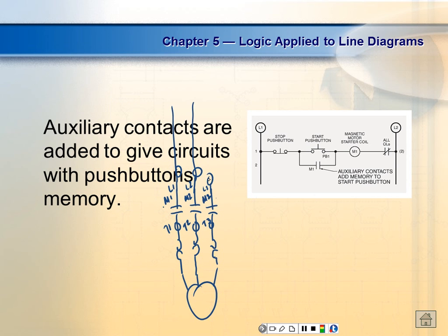what could the voltage be over here? 240, 480. Yeah, 480. So your lines can be like 480, right? 660 or whatever. You know, over here, this right here could be 24 volts. That's just control. That's control voltage. Of course, you still run into a lot of 120 volt stuff, but as time passes, because of the 70E standard, a lot of new control circuits now are dropping down to 24 volts. So, and that's what it is in your home. If you got an air conditioner outside, it's a 24 volt system.